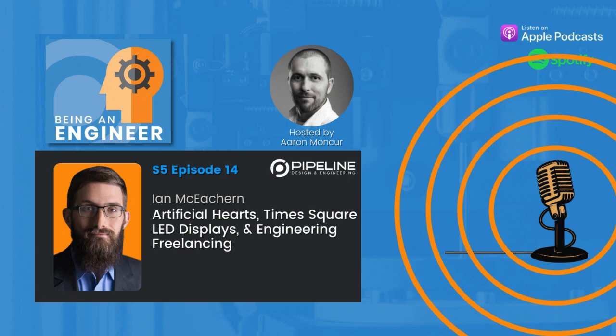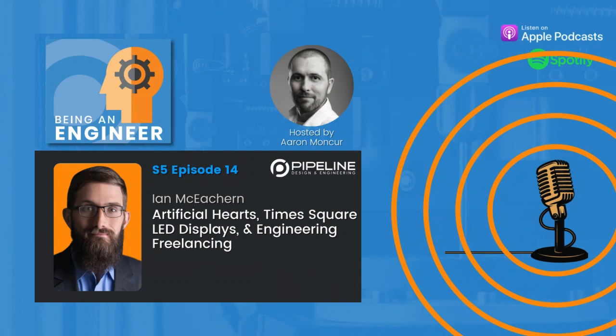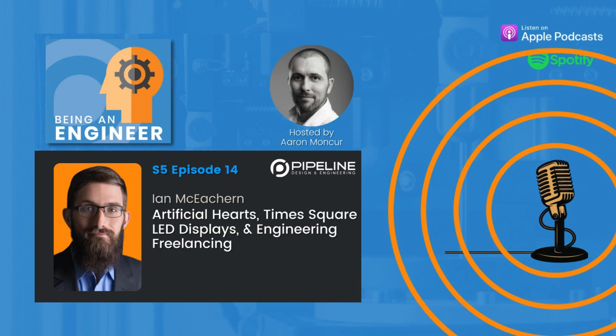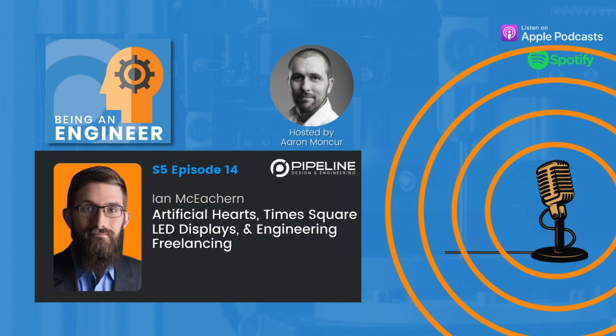Long story short, another gentleman named Dr. Wampler proved that you could pump blood not by having a bellows pump that pumps like this, but with an axial flow pump, like a jet ski, where you just have a channel and a propeller spinning inside of it. And as long as you design things certain ways and run it a certain way, you don't get too much hemolysis, which is destruction of the red and white blood cells.